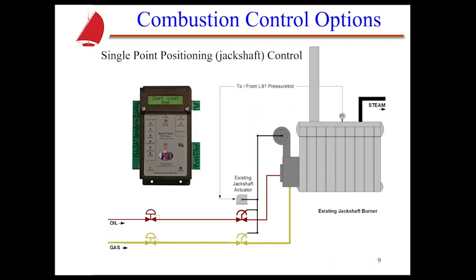So if we're talking about single point positioning or jack shaft control, what you'll normally have is, for instance, a flame safeguard, okay? And that flame safeguard will have what we call a modulation circuit built into it, which is usually just dry contacts. Those dry contacts through the startup sequence will make sure that the mod motor is at a full open position due to a switched input. When it drives that mod motor to wide open for purge, that will be verified. Then it will verify again through the switches, will drive that jack shaft or that mod motor to the low fire position and verify that for proper light off. So you'll have dry contacts in the flame safeguard that actually operate that mod motor.